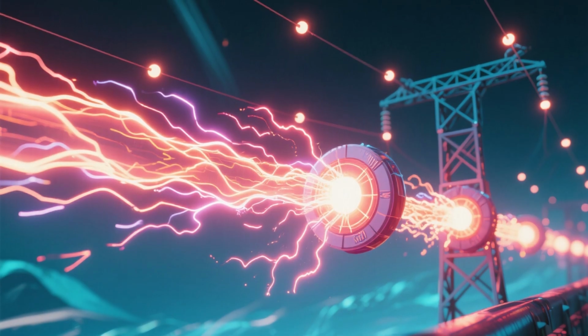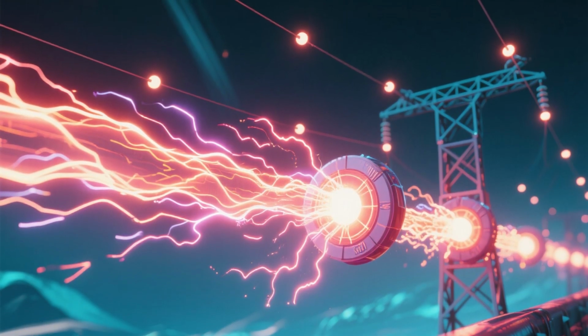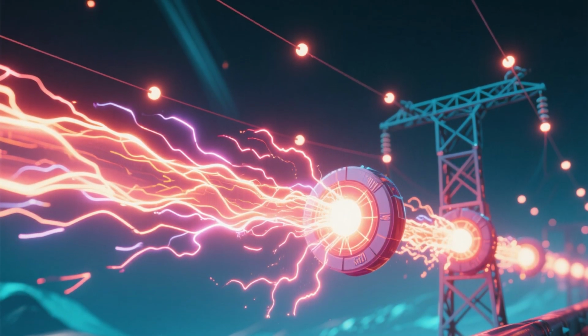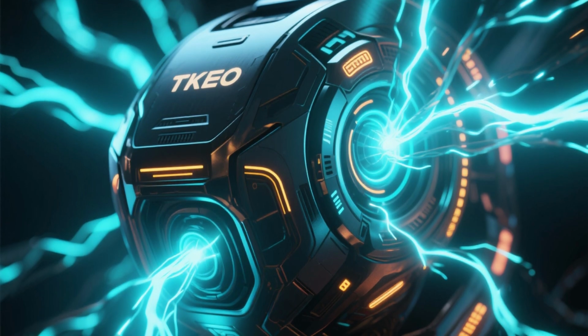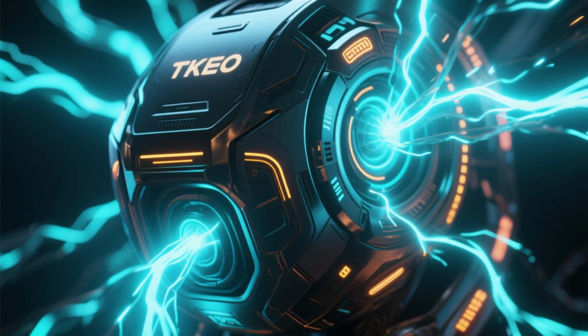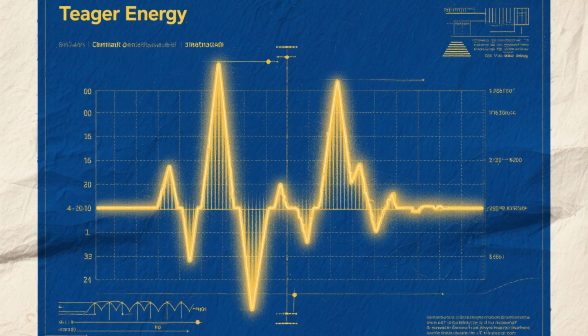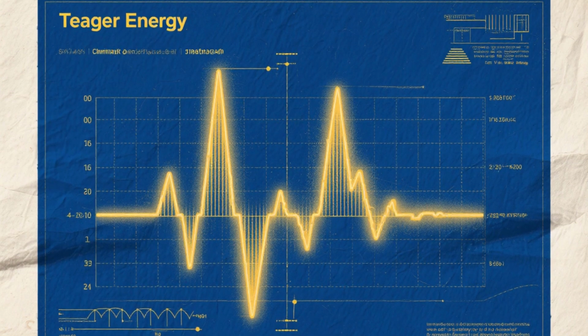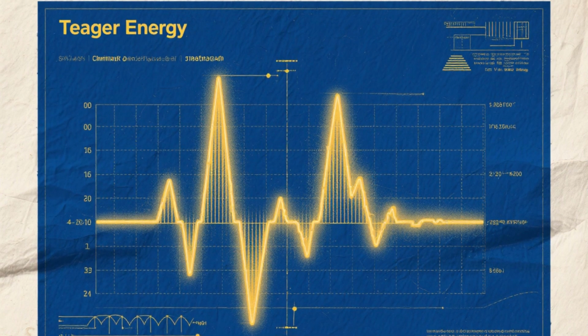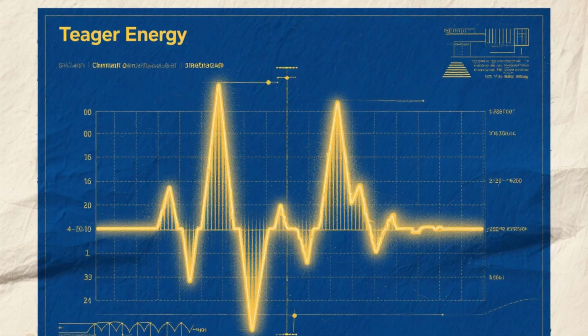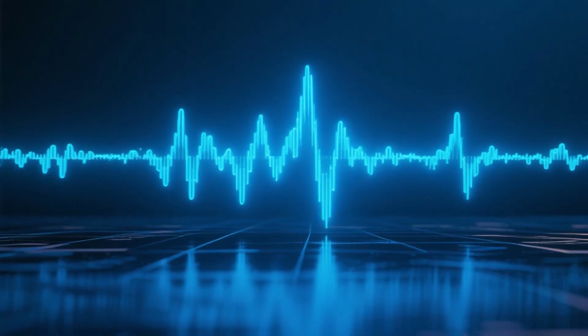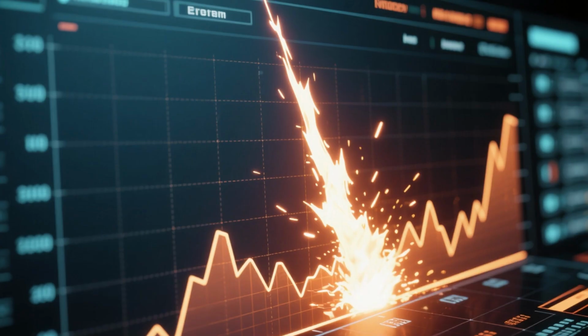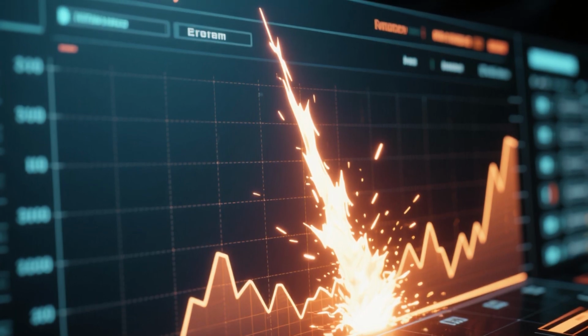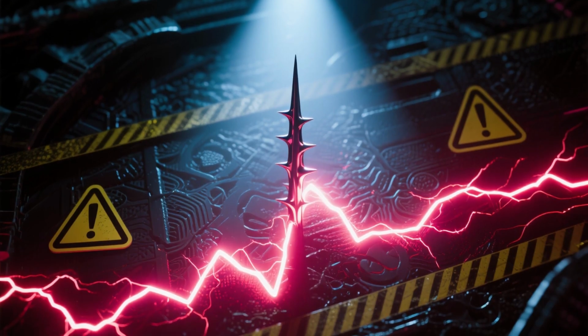When a fault occurs, it releases a burst of energy that propagates through the transmission line. The TKEO is exceptionally sensitive to this sudden release of energy. By applying the TKEO to the voltage or current signals measured at the relay location, we can generate a new signal, the Teager energy profile. Under normal conditions, this energy profile is low and stable, but at the very instant a fault begins, the energy profile exhibits a massive sharp spike. This spike is a clear and unambiguous indicator of a fault.